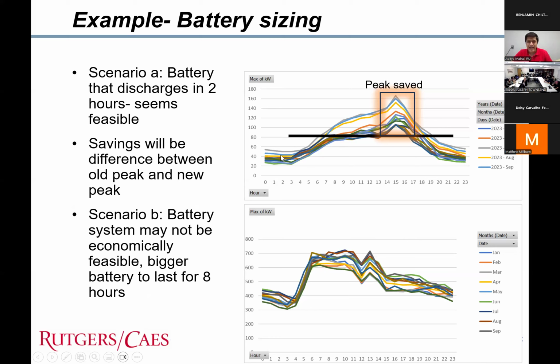Two ways. I can either charge it at night so that it's not affecting my peak demand, imagining this line goes up a little bit, so my peak demand is not increasing. However, my kilowatt hours are increasing because I'm charging my battery, but then I'm using the same kilowatt hours here. So it kind of sums out if they have a flat kilowatt hour rate - I'm not increasing any demand charges. I'm charging my battery, and then using it to reduce from 160 to 80.